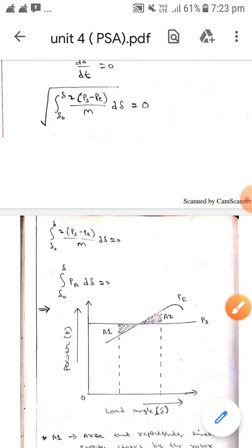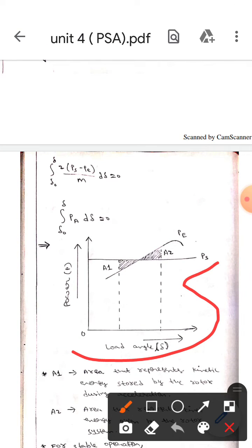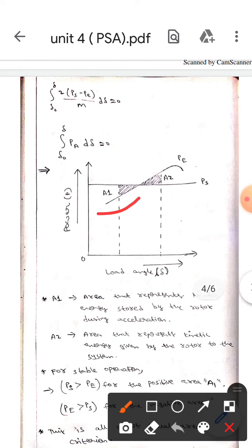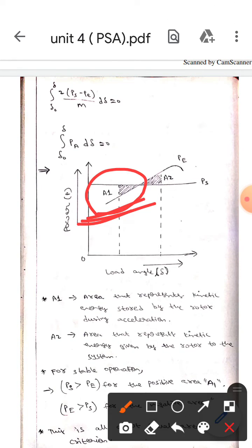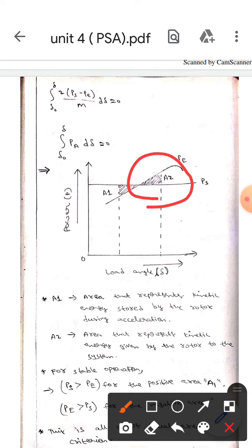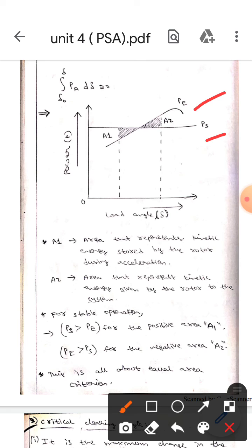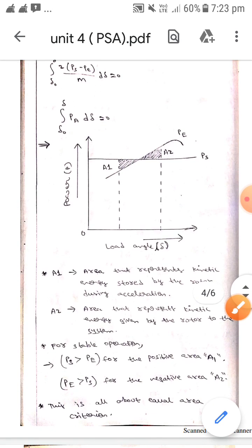the integral from δ₀ to δ of Pa dδ equals zero. Here this is the diagram for the equal area criterion. Area A1 represents the kinetic energy stored by the rotor during acceleration, and area A2 represents the kinetic energy given by the rotor to the system. For stable operation, Ps should be greater than Pe for positive area A1, and Pe should be greater than Ps for negative area A2.